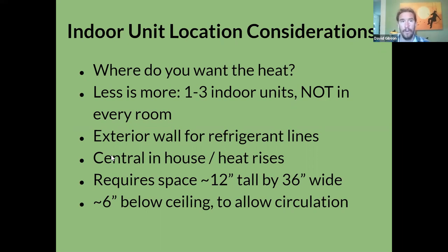I've seen them put in hallways where the owner thought that the heat would rise, like facing into the stairwell, and it kind of just short circuits and it's pulling back in the heat. And so it thinks that it's heated the whole space when in reality it hasn't distributed the heat very well. And so the bigger and more open the space is, the better off the system will be. And they really can distribute heat well in a house.